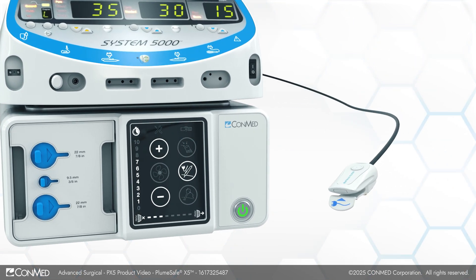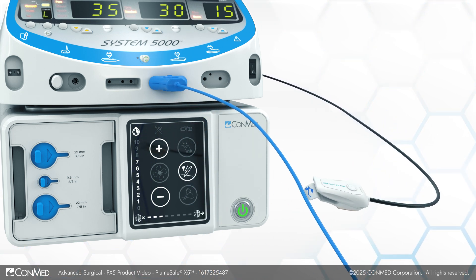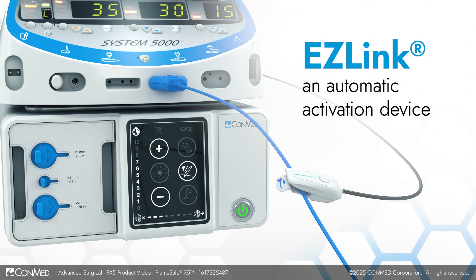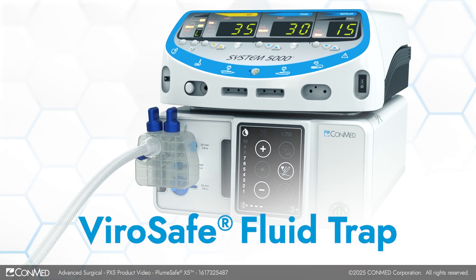ConMed offers a broad portfolio of products and accessories tailored to your surgical needs. EZLink, an automatic activation device, can be used to remotely turn the evacuator on and off, saving filter life. The ViroSafe Fluid Trap is designed to capture fluids and maintain the integrity of the filtration system.